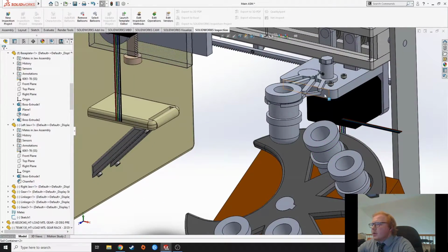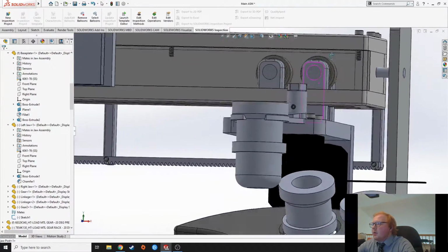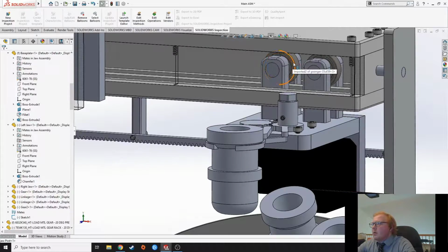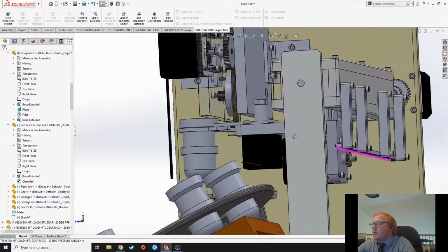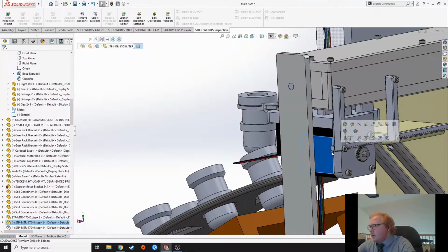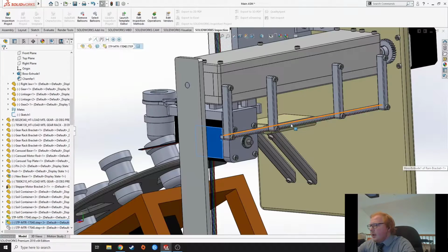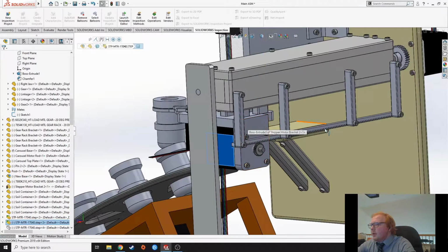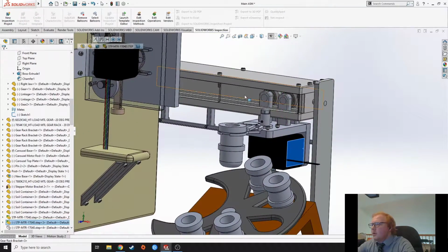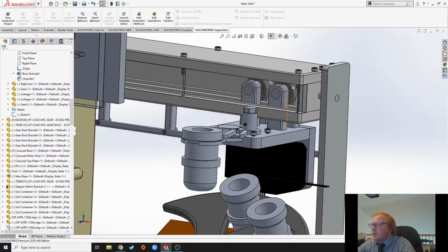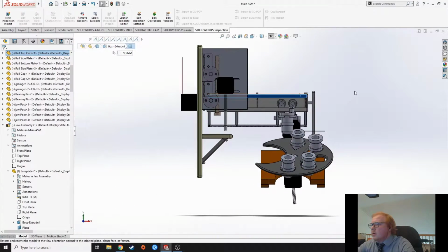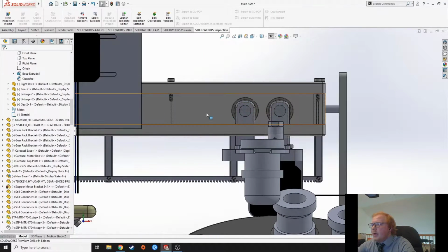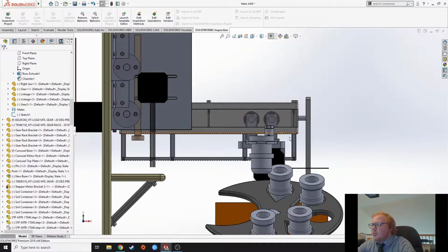And then from there, once the sample container is retained in the jaws, this entire assembly is moved by this second stepper motor here, which rotates this gear and transports the entire assembly down this track. And I made this transparent here so we could see how the bearings allow for very smooth movement up and down the rail.